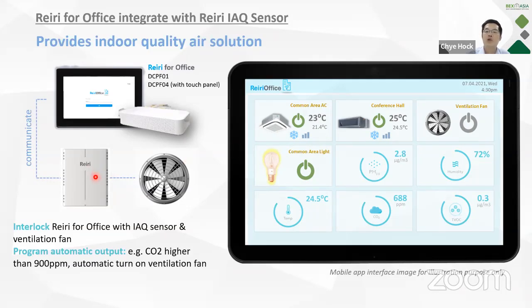When the CO2 rises above a certain preset level, like 900 ppm, in the room, a command is sent to the ventilation fan to turn on, bringing in more fresh air from outside. This helps improve the indoor air quality and reduce CO2 in the room - this is what we call smart control by our Reiri controller.